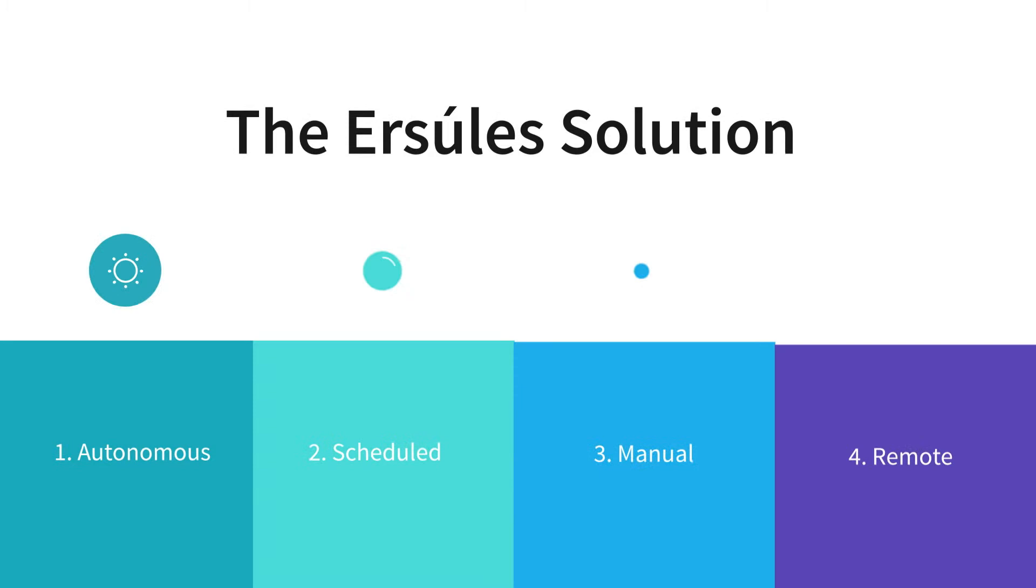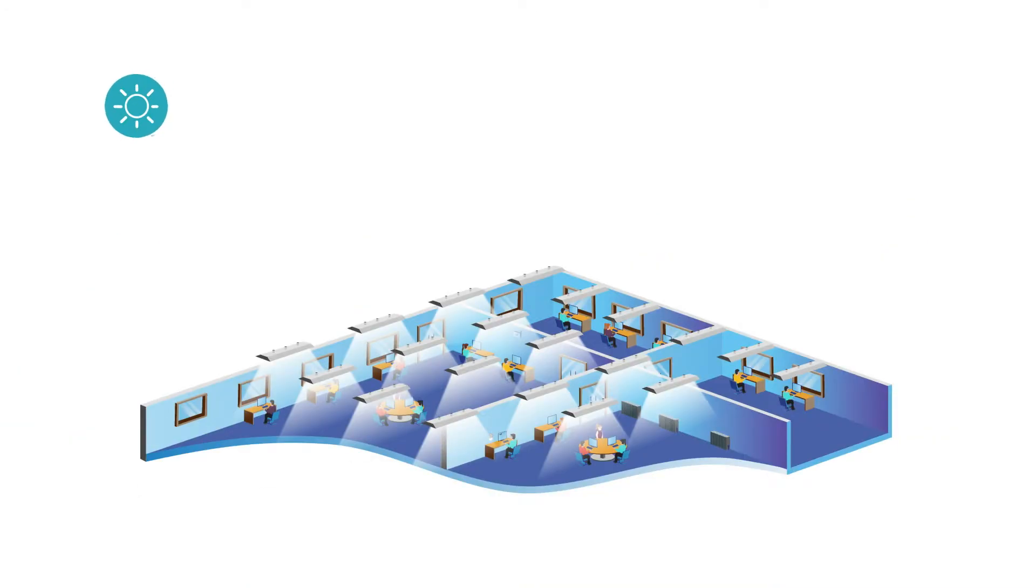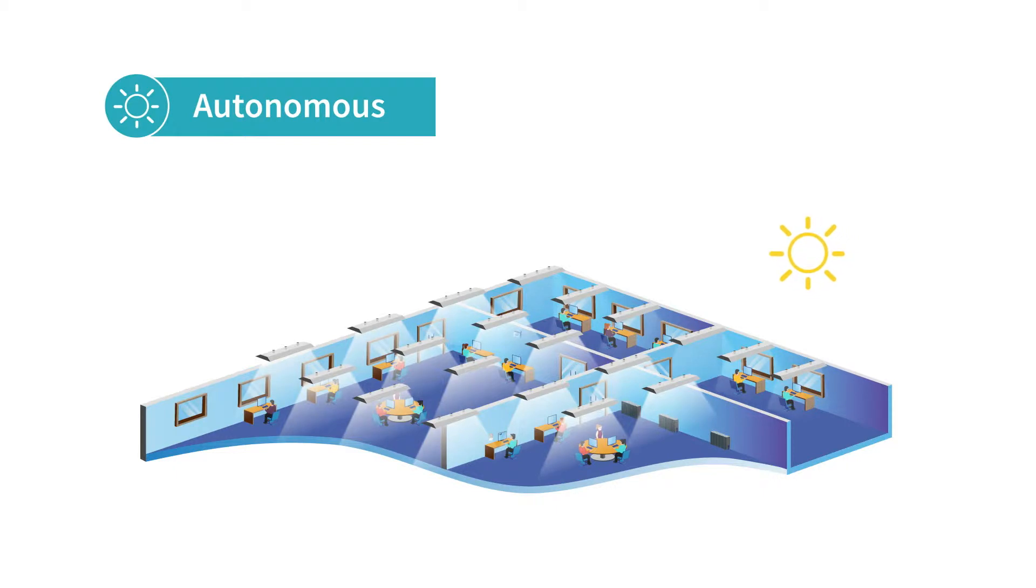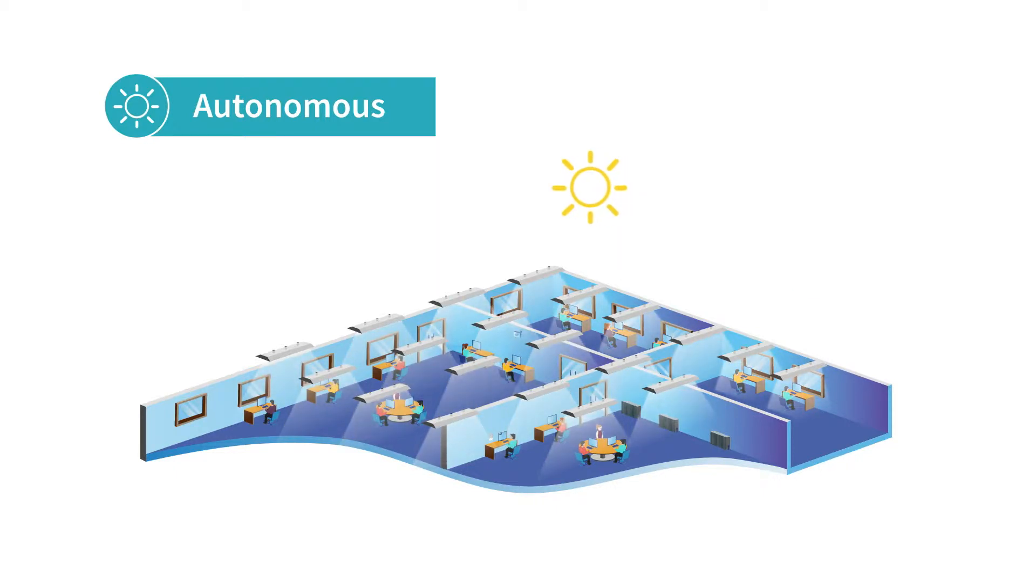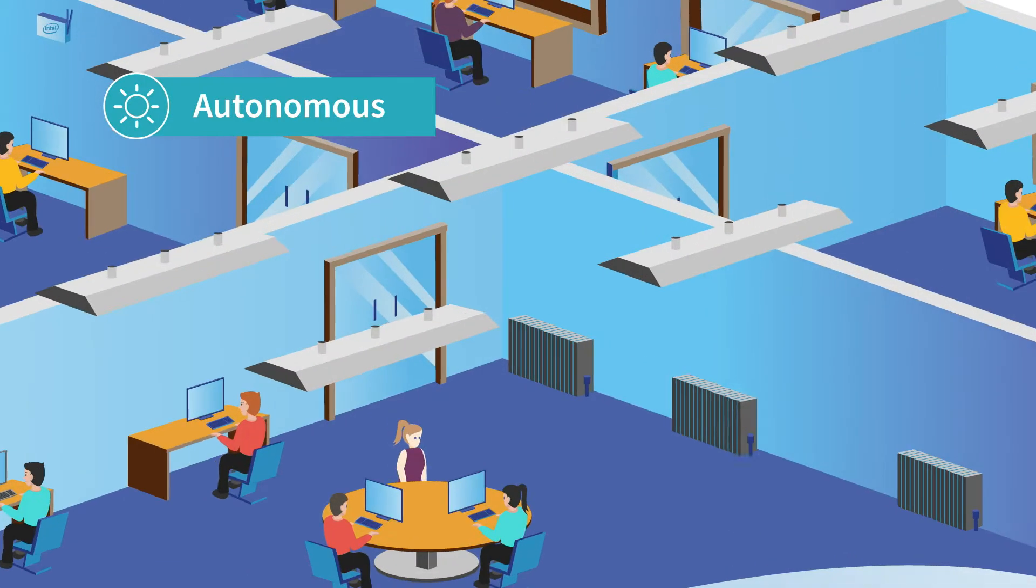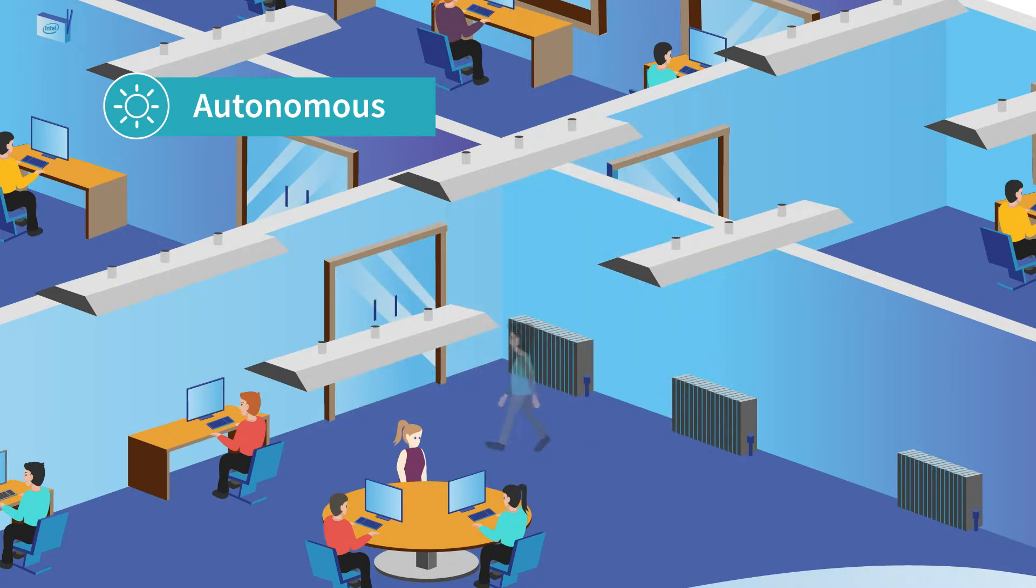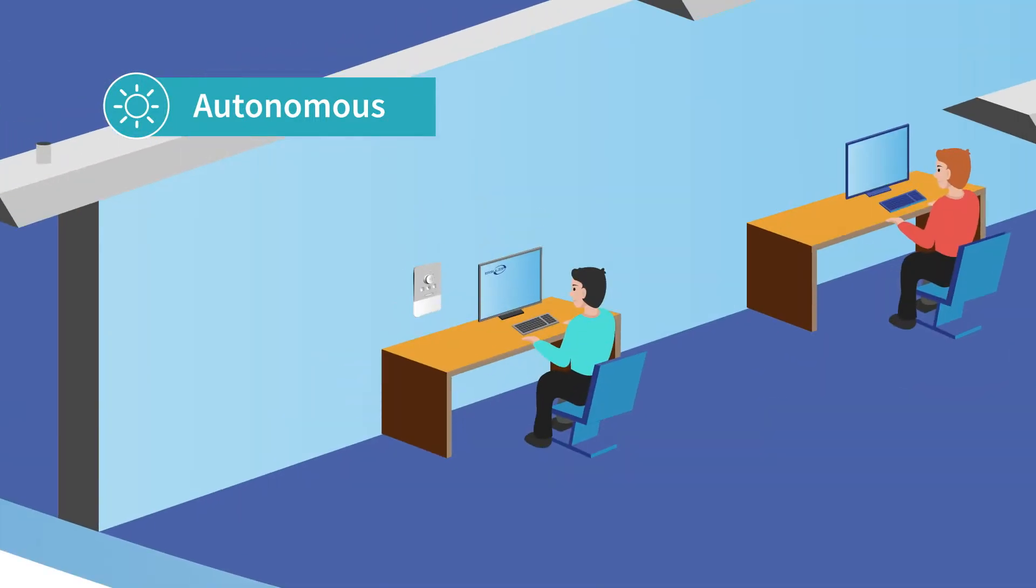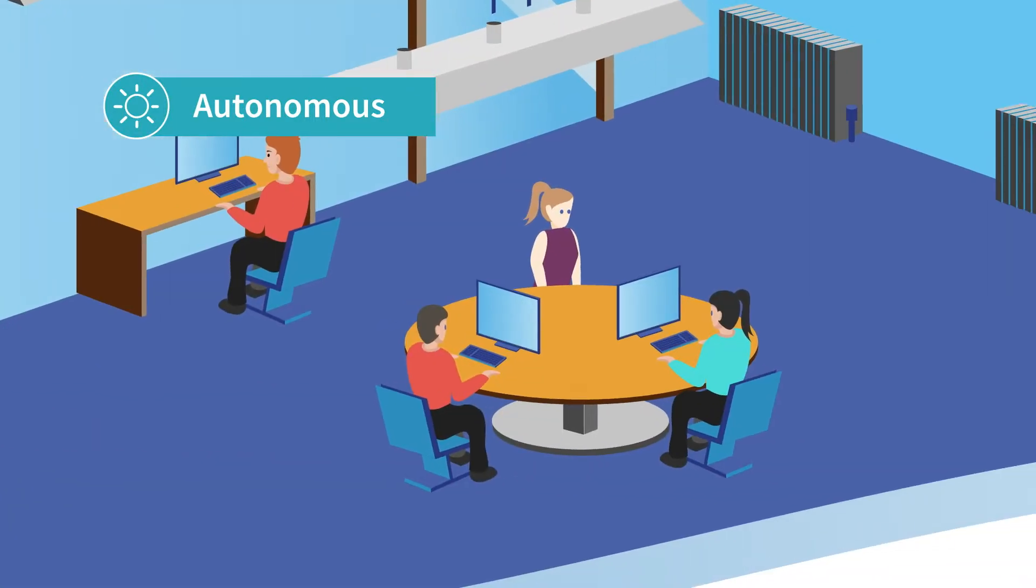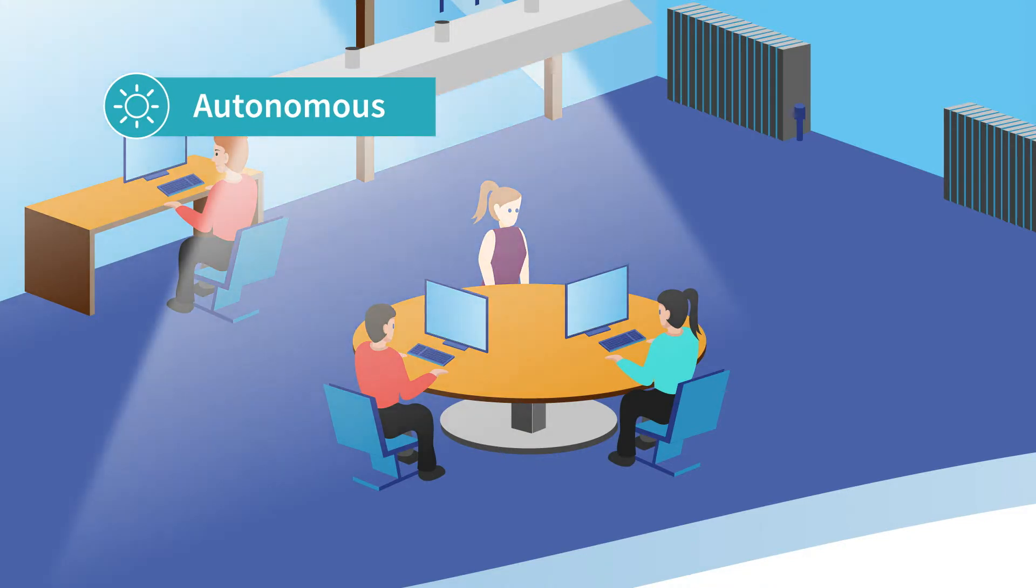The Ersúles solution allows you to control lighting in your facility in four different ways. The first approach is autonomous and relies on the Ersúles lighting control algorithm. Here, the lighting is controlled via daylight harvesting that detects ambient light levels and alters fixture output accordingly, or occupancy sensing that turns lighting on or off based on whether an area is in use. Task tuning adjusts task and ambient lighting in a space to meet specific user preferences.